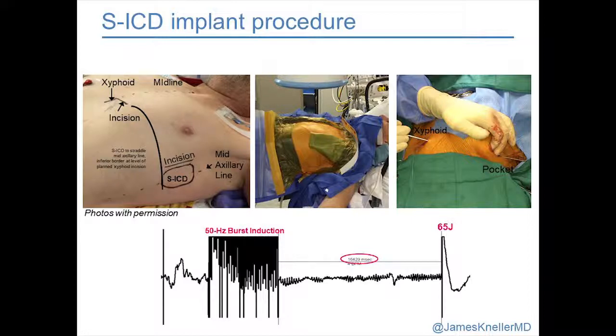Defibrillation threshold testing, the device can deliver a 50 hertz burst, causes ventricular fibrillation, DFT times are longer, charge times are longer, here 18 seconds. With our positioning and knowing it's perfectly positioned every time, we've never missed a DFT at 65 joules. The second shock is 85. We've never missed one at 65. And it's all about making sure that myocardium is sandwiched by that defibrillator system in that particular patient.